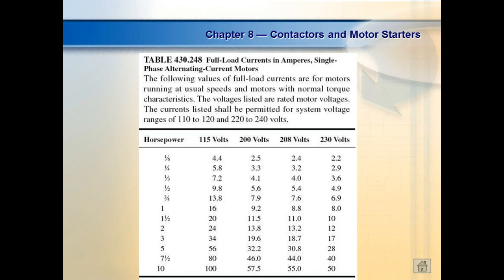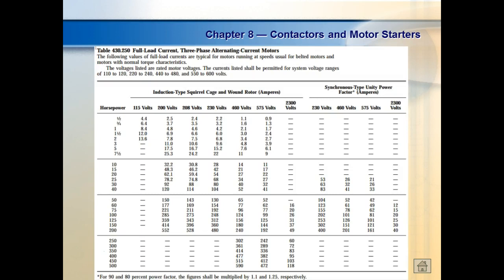Now these are single phase, so this would be where I could go if I didn't have the nameplate, if the nameplate on the motor was missing. If I've got the nameplate of the motor, that's what you should use, right? But the nameplate of the motor is probably the first thing that goes the first time they ever have it rebuilt. And then this is three phase. This is table 430.250. And this gives us typical full load currents for different horsepower motors.